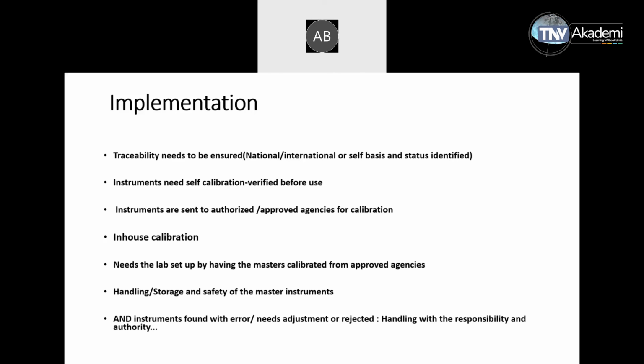By looking at the list and the status itself, the auditor should be clear whether it needs further investigation or not, whether it needs only a tally with the test certificate, or whether we need a national traceability certificate also or not. So there are different ways of doing it. Organizations use different kinds of tags and labels, and they write all this on the instrument itself. Even the outside calibration agency will put a tag on it. A similar practice can be followed for self-calibration or in-house calibration.